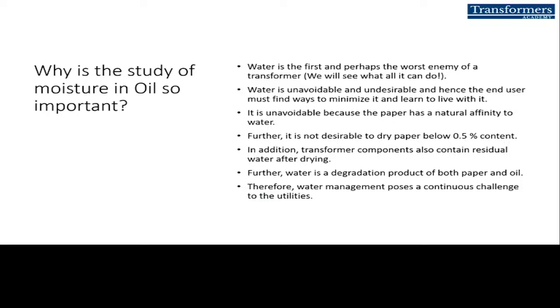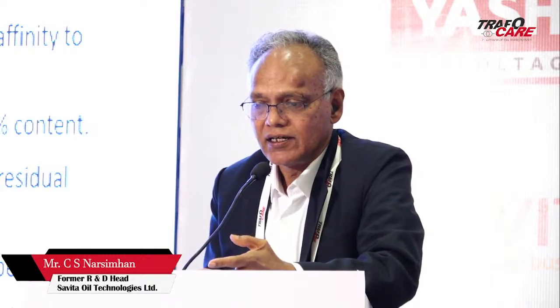Why is it important to study moisture in oil? Because water management poses a continuous challenge to utilities. Water is the first and perhaps the worst enemy of a transformer. At the same time, there is very little you can do about it. You cannot avoid it, it is not avoidable. It is undesirable but unavoidable. Paper as well as oil will always have some moisture, and in fact it's desirable to have 0.5% moisture on paper to maintain its integrity.